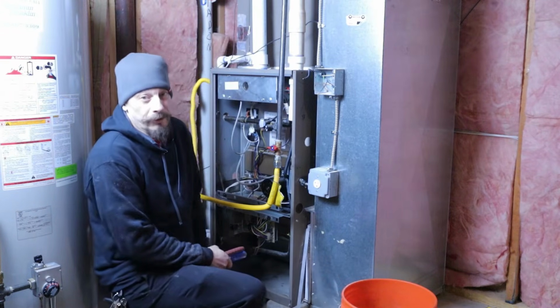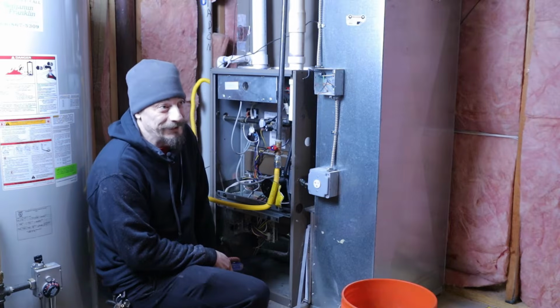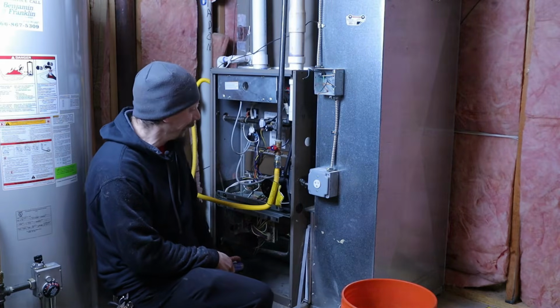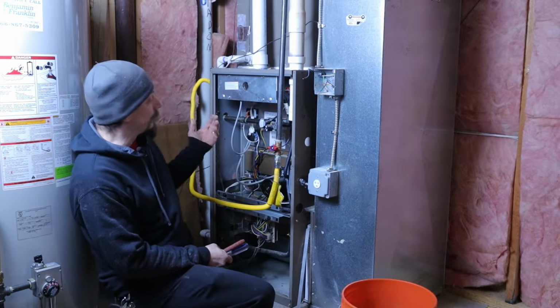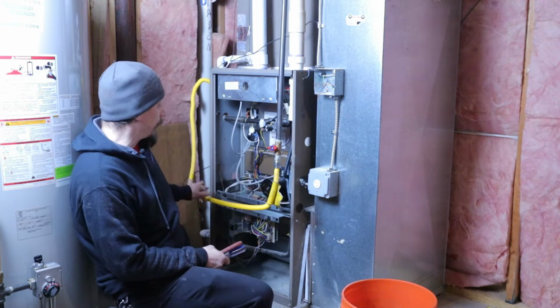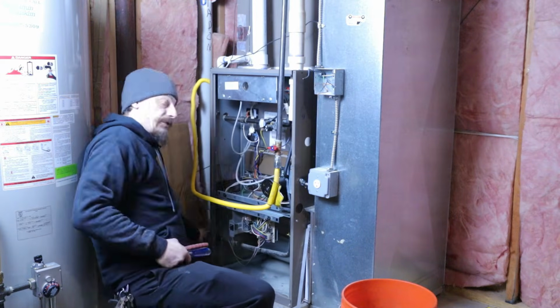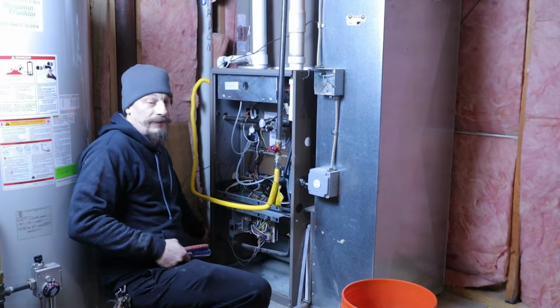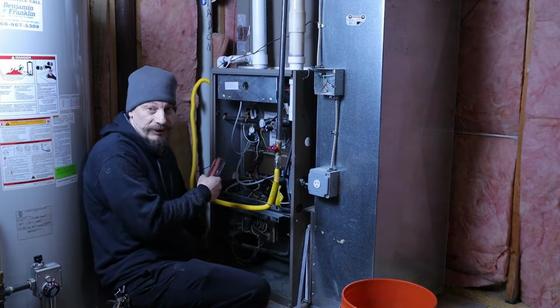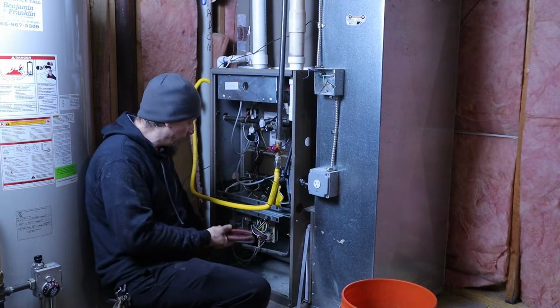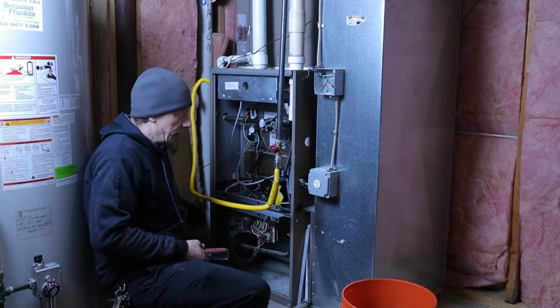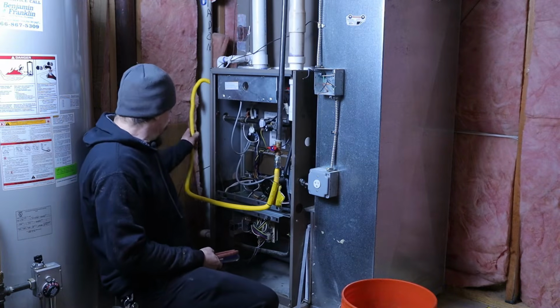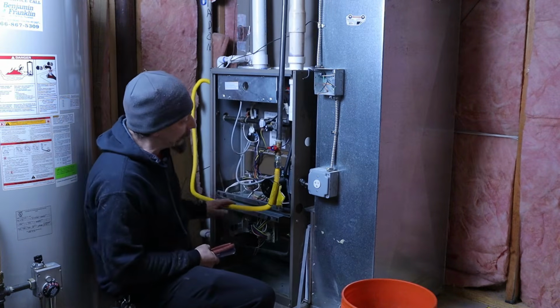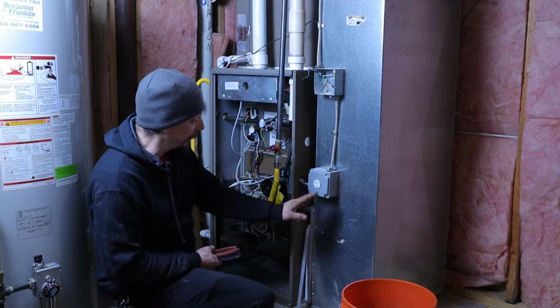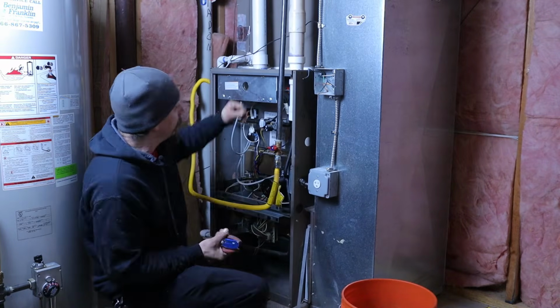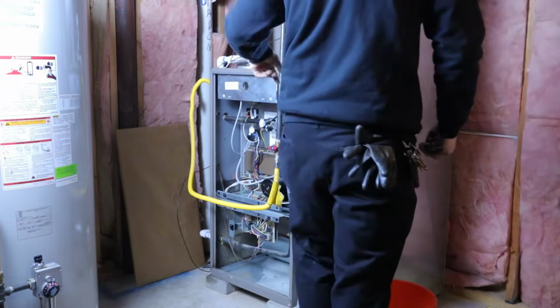So we're pulling out a York and putting in a Goodman. Not sure how I feel about that, but it is what it is. So what we're gonna start doing is I'm gonna have Juan over here start disconnecting the gas line. There's some PVC behind here with a condensate pump. That's for the condensate that the furnace generates. It's a 90%, so it makes water all the time, drains out down here. So we're gonna disconnect that. Have him disconnect the gas. I'm gonna start working over here on disconnecting the electric and the return. All right, so you go ahead and get started on that.